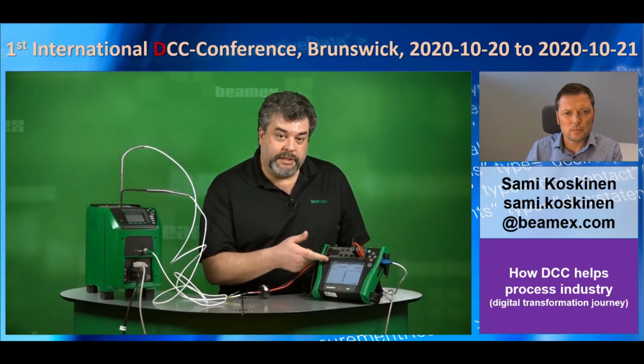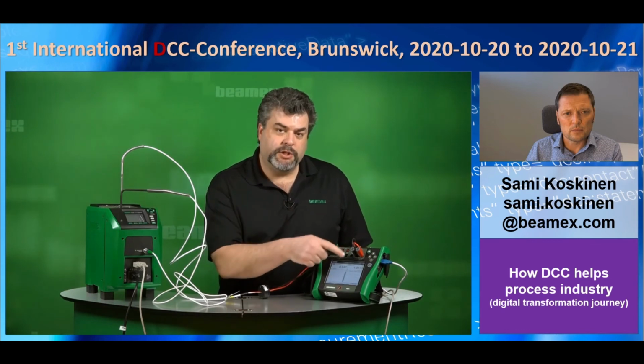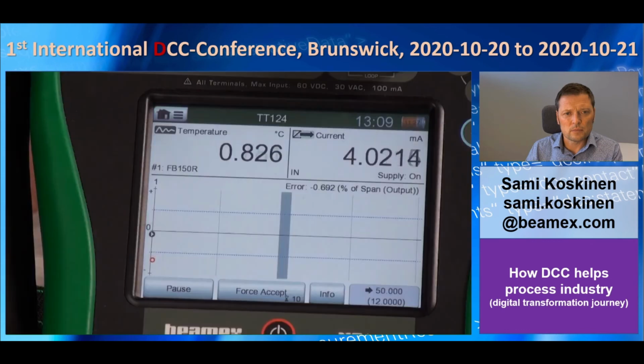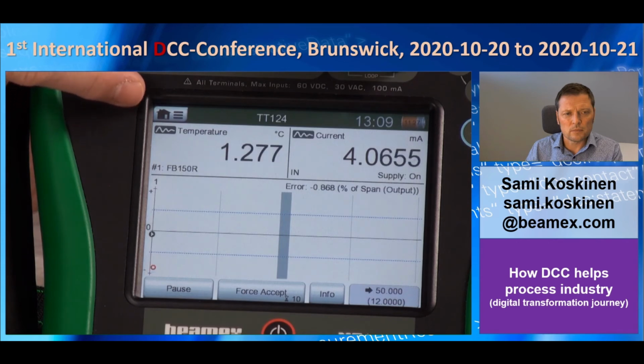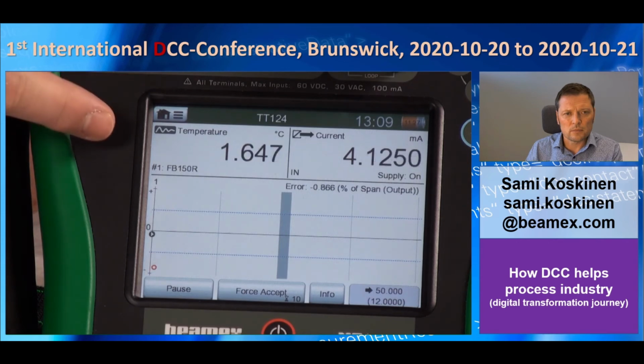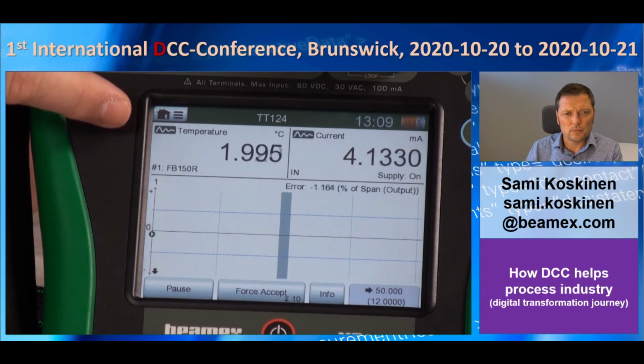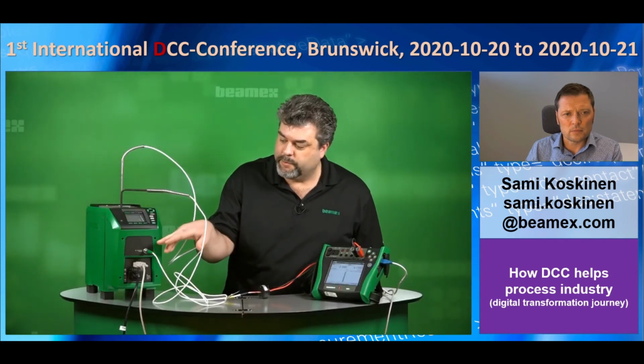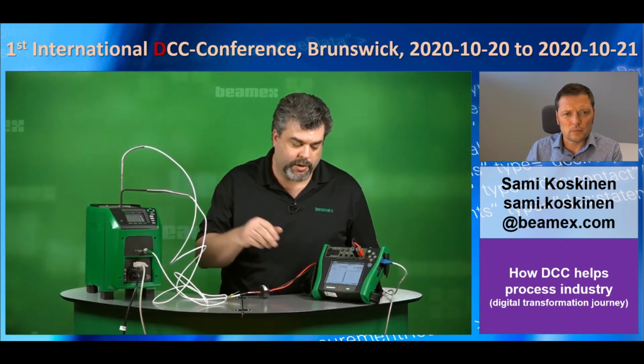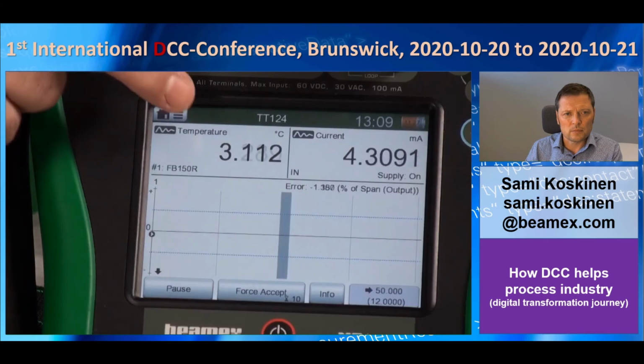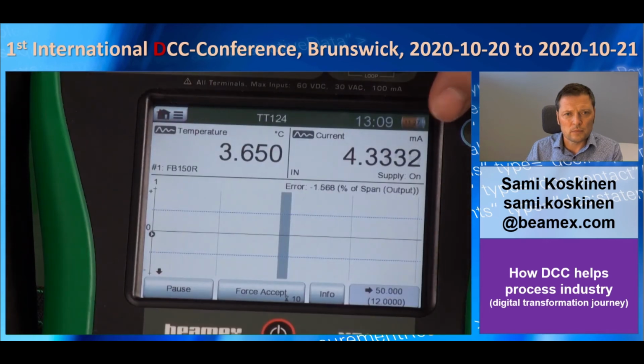While this is increasing in temperature, let me explain what's going on with the screen here. On the top left, you have the input. It tells us that we're hooked up to a temperature source. It tells us we're hooked up to an FB150R. The R means that we have a reference probe attachment right here in the front. And it's also in degrees C. Now the top right is the output, so that's where we're measuring milliamps. And it tells us that the supply is on.